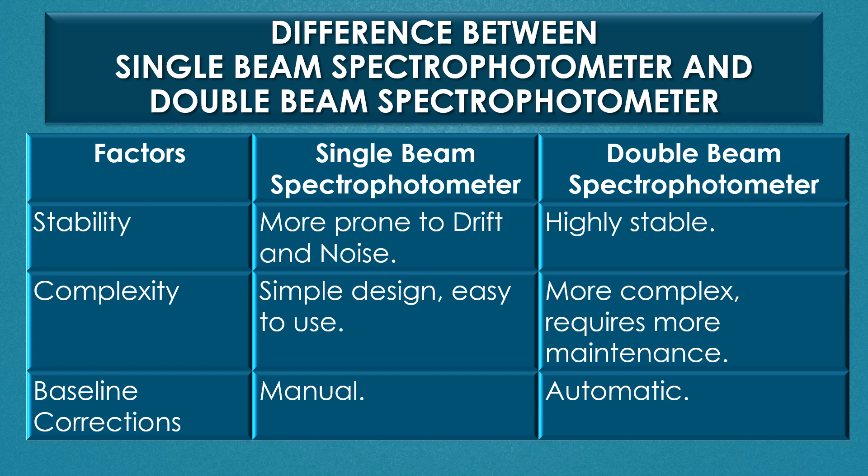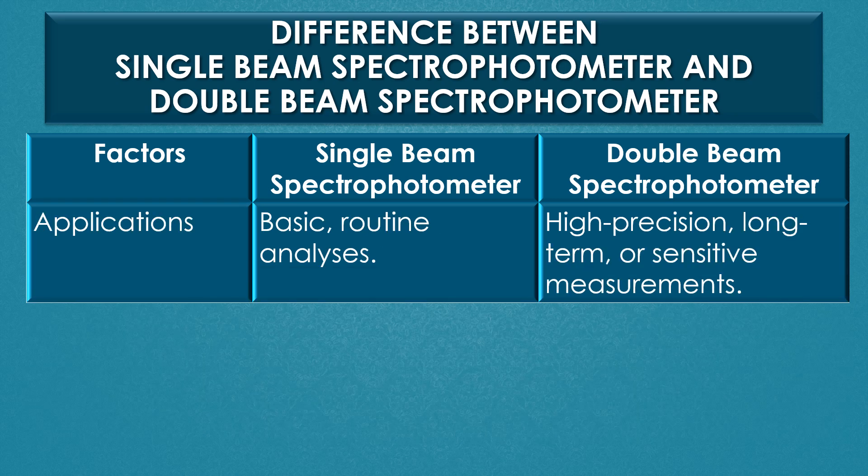Next, baseline corrections: in a single beam spectrophotometer, baseline corrections will be done manually, but in a double beam spectrophotometer, the baseline corrections will be done automatically. Finally, applications: the single beam spectrophotometer is used for basic and routine analysis, but the double beam spectrophotometer is used for high precision, long-term, or sensitive measurements.